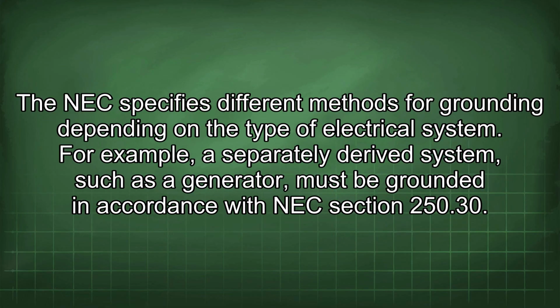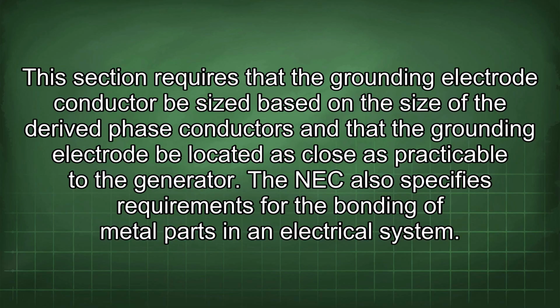The NEC specifies different methods for grounding depending on the type of electrical system. For example, a separately derived system, such as a generator, must be grounded in accordance with NEC section 250.30. This section requires that the grounding electrode conductor be sized based on the size of the derived phase conductors and that the grounding electrode be located as close as practicable to the generator.